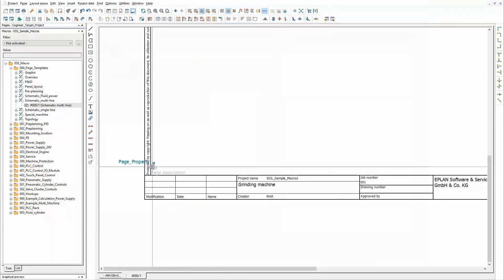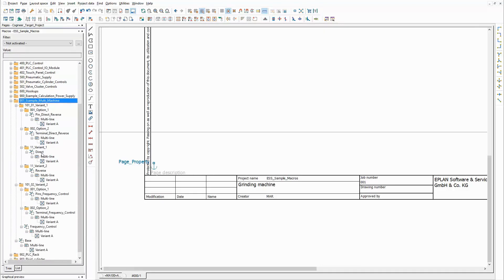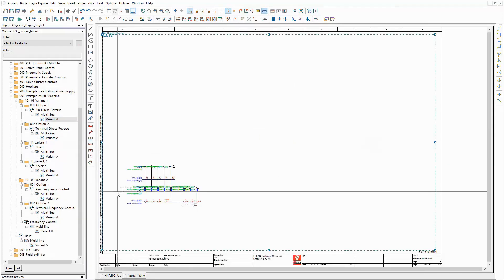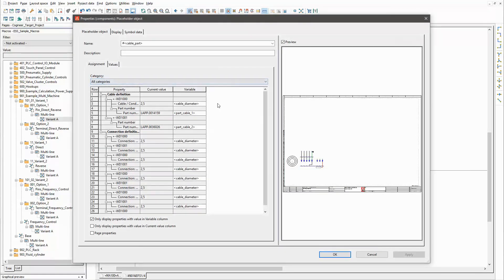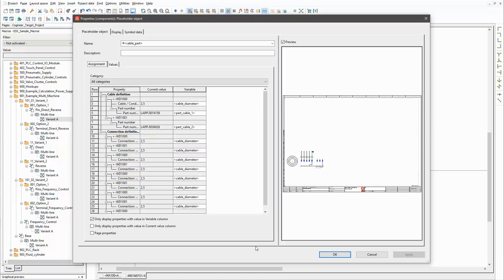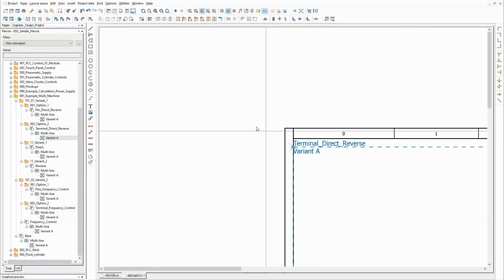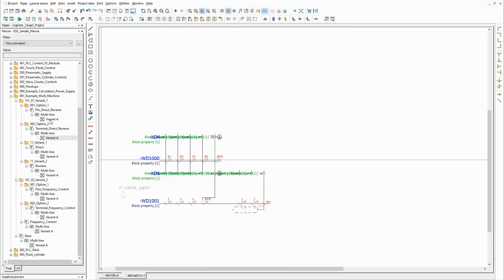Now let's have a look at the macros that are used for my drive. The partial circuits for all the options are split into several macros. This one contains all the parts that are necessary for the connection type 'pins' in combination with the direct or direct with reverse drive control. There is a placeholder object that contains two value sets. Depending on the selected power of the drive, the according value set will be used for the referenced macro properties. The next macro is used in the same combination, but for the connection type 'terminals'. The placeholder object is the same as in the macro before.